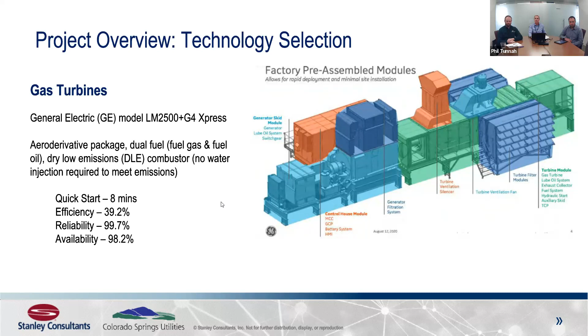In terms of the ambient temperature swings this site experiences, the package included an inlet cooling system. In terms of reliability, on your hottest days, if you're not conditioning the inlet air into your gas turbine, you're going to lose megawatts available from these units.